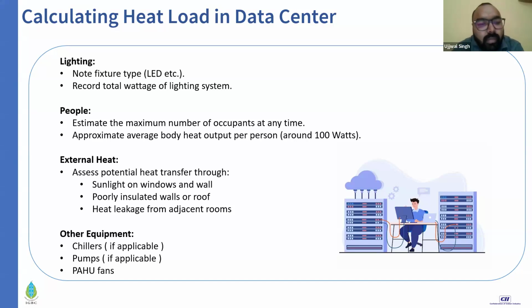For external heat, you need to either run a small simulation with the building architecture in place using a simulation tool, or use a normal Excel sheet with the U values of the wall, U values of the glass, and the amount of sun radiation falling, to roughly calculate the external heat load. Though compared to the heat load generated inside, it's not much in value.